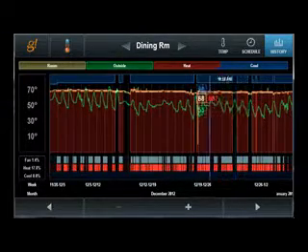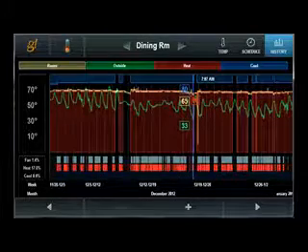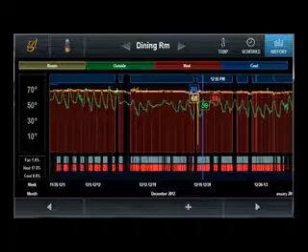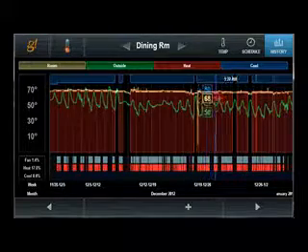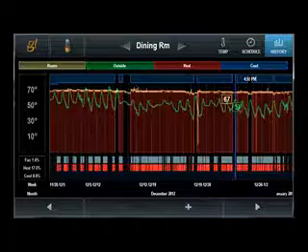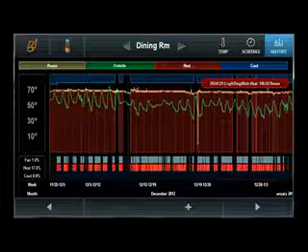It just was running all the time. So the temperatures are getting down there. It's getting down to 38 degrees. Here it got down to 38. So it's cold, but it should not be running that much. And we can observe this in just opening up our history log.